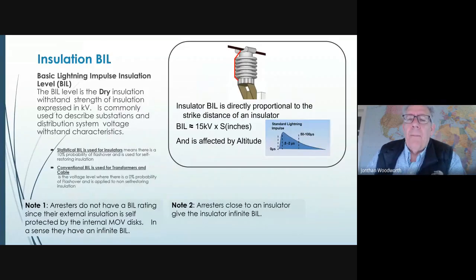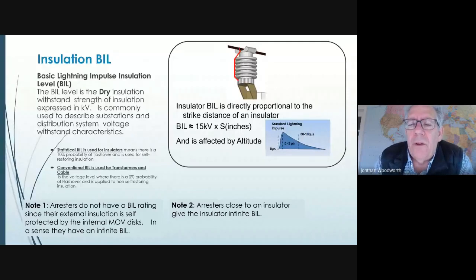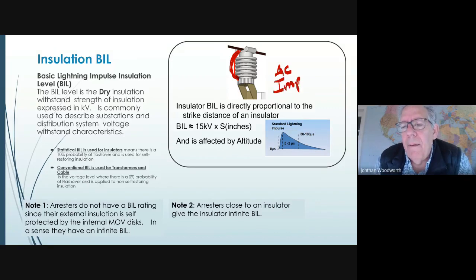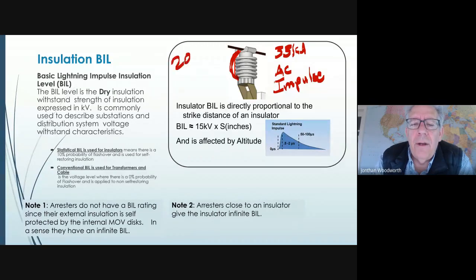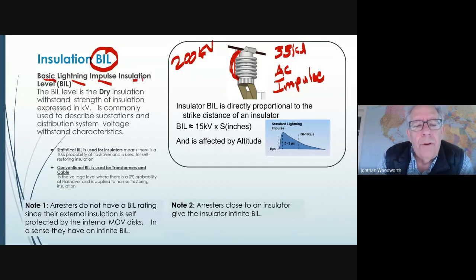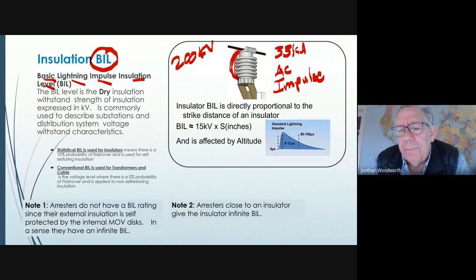Insulators have a couple of important characteristics that I want to talk about. One is that they will always flash over at some voltage level. Insulators are usually rated by the AC voltage that they will hold off, but they're also rated by the impulse voltage that they'll hold off. So an insulator that is used on, say, a 33 kV AC system will often have a 200 kV withstand voltage. And this is called the BIL, or the basic lightning impulse insulation level. In IEEE terms, it's BIL.